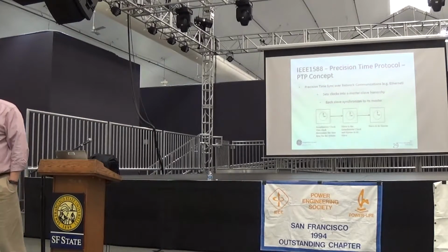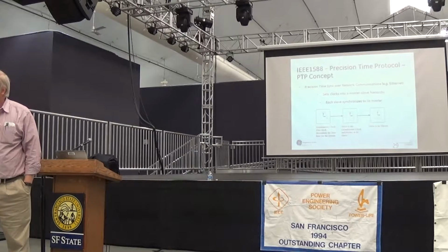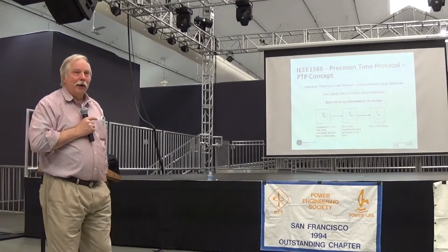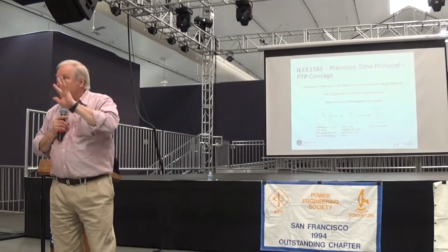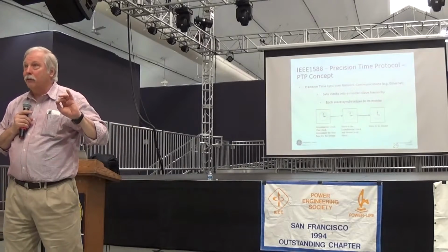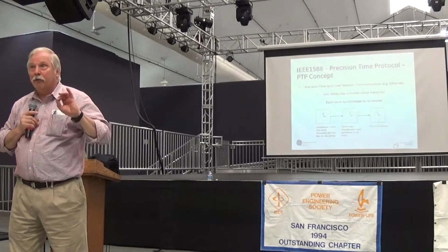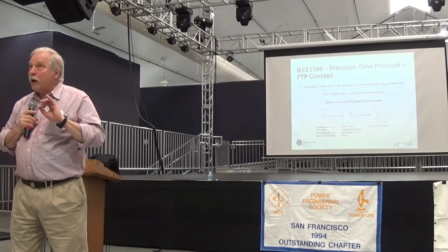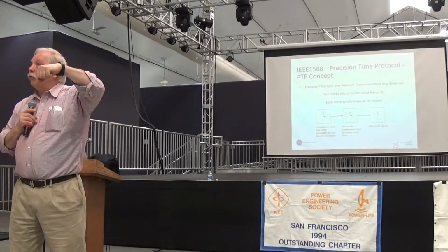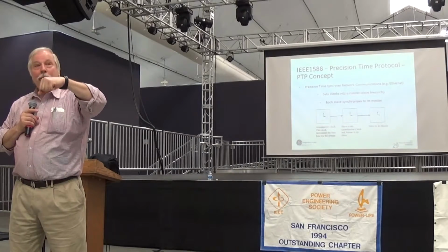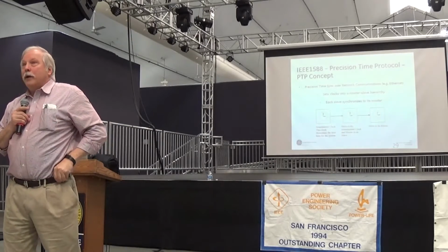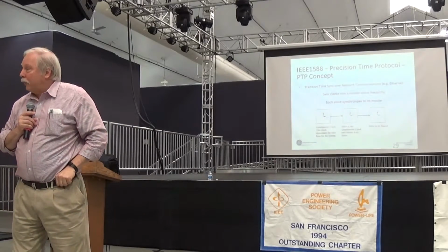Where do we see this applied? Process bus. One of the architectures of process bus, and there are multiple architectures that can be implemented as part of the 61850 process bus standard, is where the Grand Master synchronizes the relay, and then the relay synchronizes the merging units within a zone of protection.